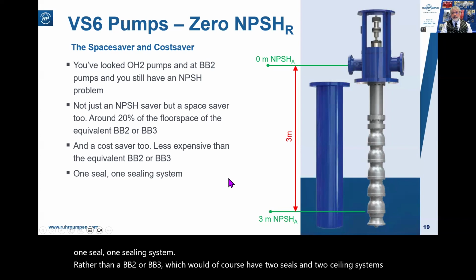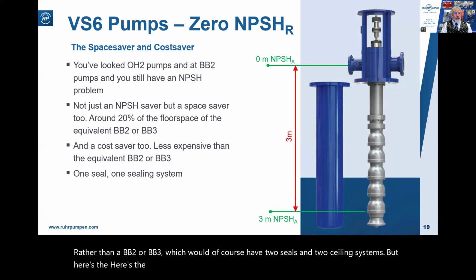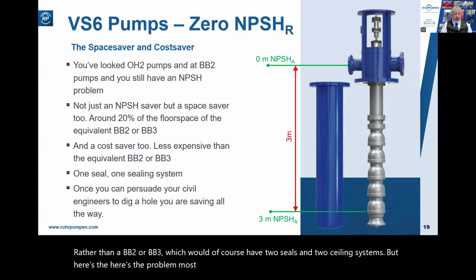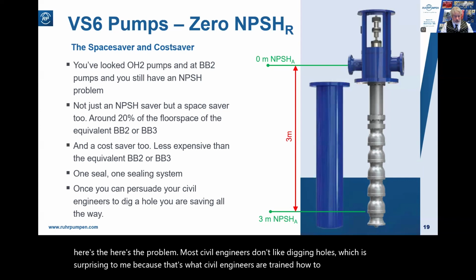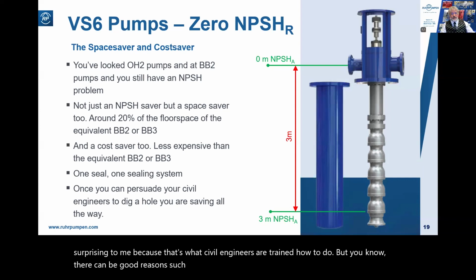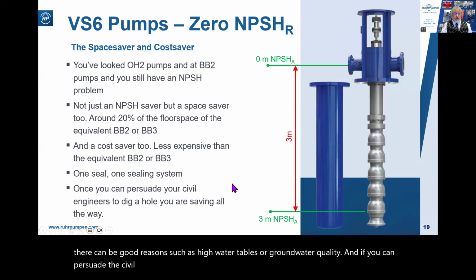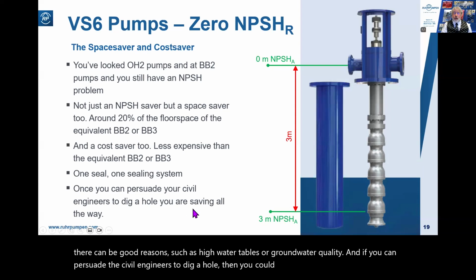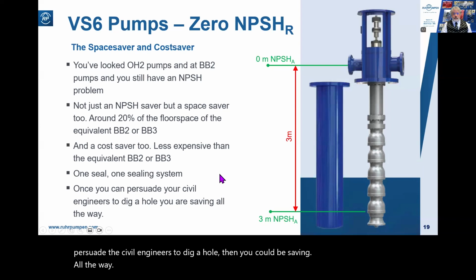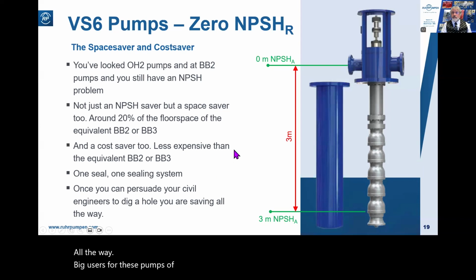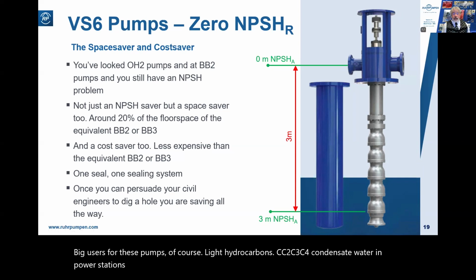But here's the problem. Most civil engineers don't like digging holes, which is surprising to me because that's what civil engineers are trained to do. But, you know, there can be good reasons, such as high water tables or groundwater quality. And if you can persuade the civil engineers to dig a hole, then you could be saving all the way. Big users for these pumps, of course, are light hydrocarbons, C2, C3, C4, condensate water in power stations, ammonia, and cryogenic applications, liquid oxygen, liquid nitrogen.